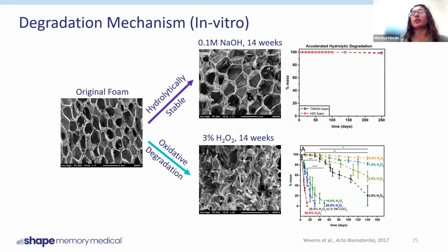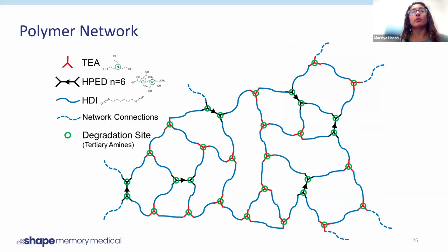But we can see at 14 weeks in 3% hydrogen peroxide, the foam is starting to look like it's melting. So the strut integrity has gone away. The membranes are starting to disappear, and it's just not holding its shape like it should be. And what we found out further through additional academic research is that these tertiary amines in our trifunctional and tetrafunctional polyols are the points for degradation. So any of these points that are circled in green is where our degradation was taking place. Oxidatively, these linkages were getting broken, and then the degradation byproducts are just getting removed from the body through your urinary tract.